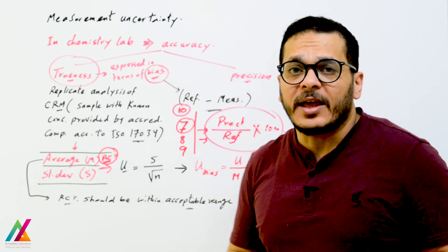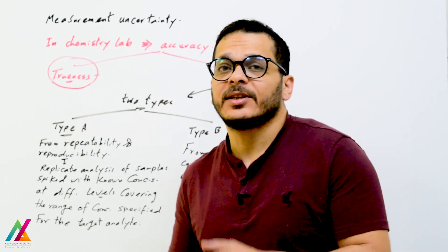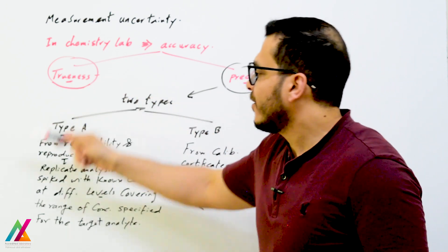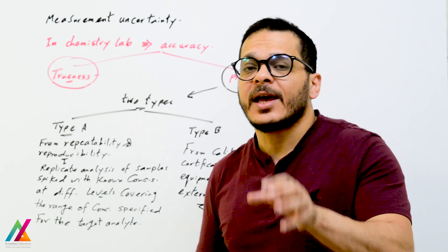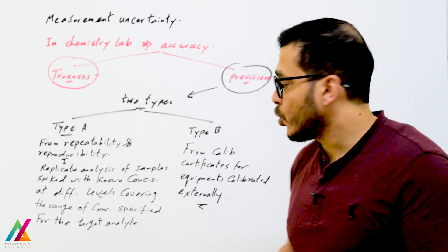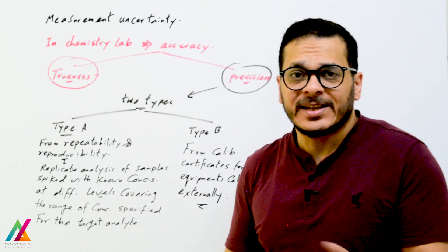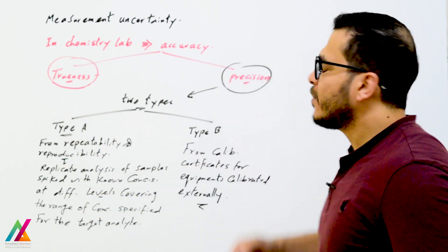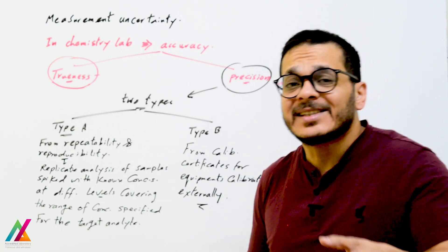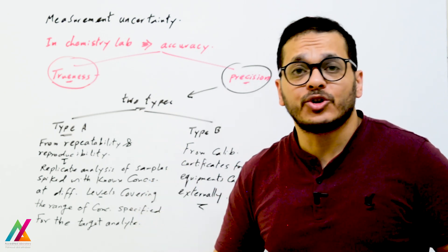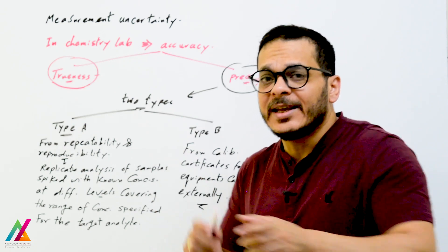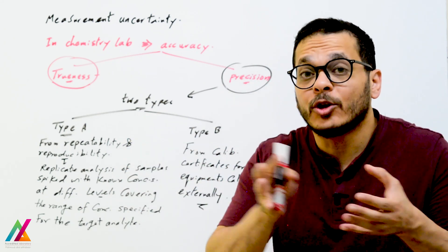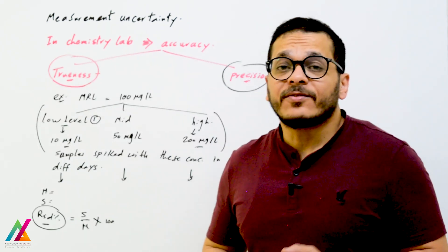For precision, it is estimated from repeatability and reproducibility. There are two types of evaluation: Type A and Type B. Type A evaluation comes from repeatability and reproducibility through replicate analysis of samples spiked with known concentration of target analytes at different levels. Type B evaluation comes from calibration certificates for externally calibrated equipment used during the whole measurement process — the certificate includes measurement uncertainty that is also added to the combined uncertainty.